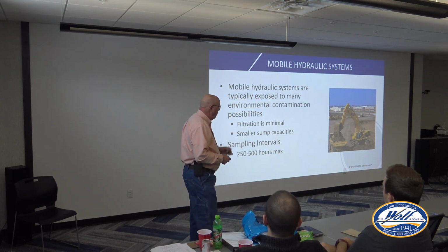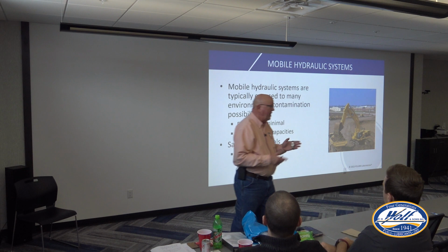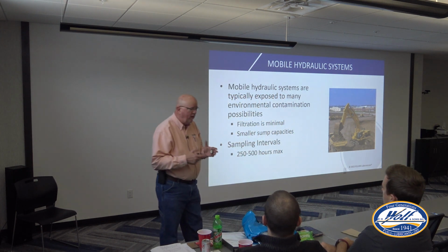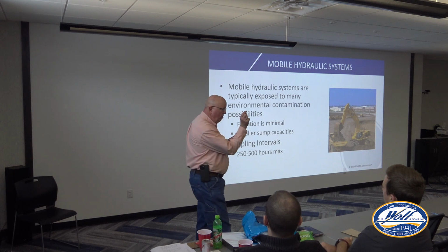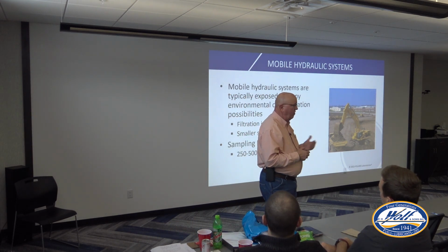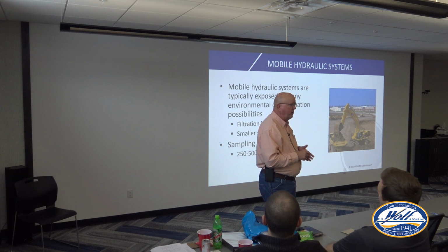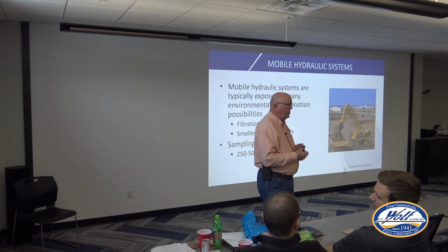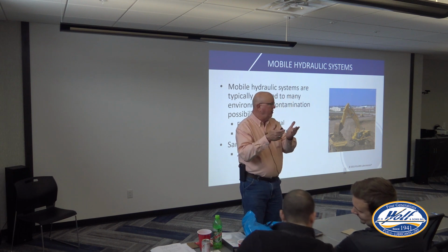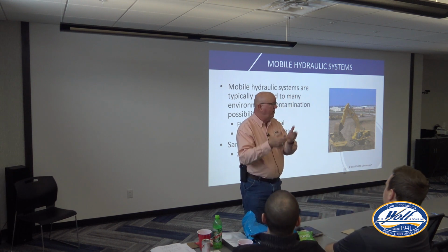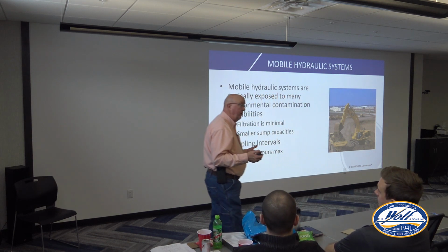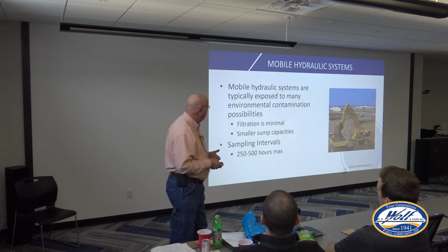He said if you get 1/4 of an inch of buildup on the outside of that reservoir, let's say it's oil and grime and dirt, you increase the temperature of that oil by 20 degrees. Well, why is that important? When we were talking about hydraulics, what did I say? Everything above 140, 18 degrees above, you cut the life of that oil in half. So if you get a 1/4 buildup on that cooling reservoir, it's going to cut the life of that oil in half.